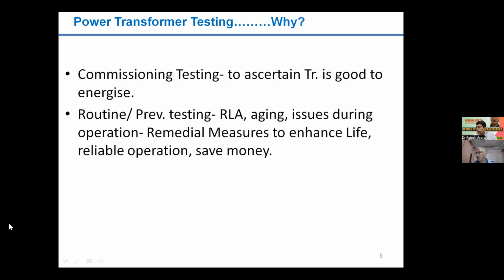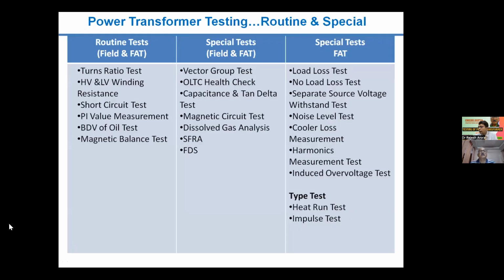Basically, these tests again may sometimes be done especially after some events on the transformer, or may be done routinely, say yearly. If we do them routinely, then the purpose of these tests is to check what kind of problems or trends are developing with the components of the transformer, like insulation health. So in short, it may be described as residual life assessment, RLA, aging. And accordingly we take remedial measures, corrective actions to service the transformer, to enhance its life, because we know that the transformer is a costly equipment, and accordingly we should keep track of its health.